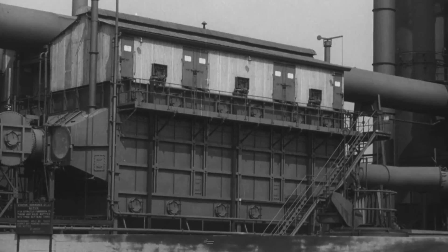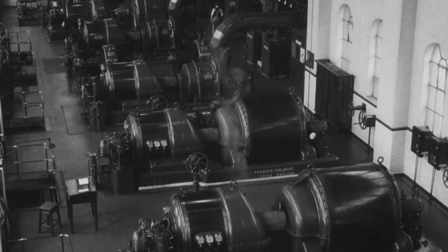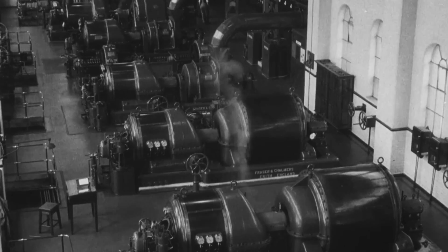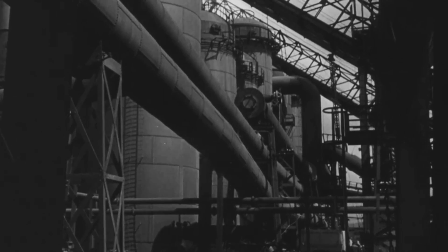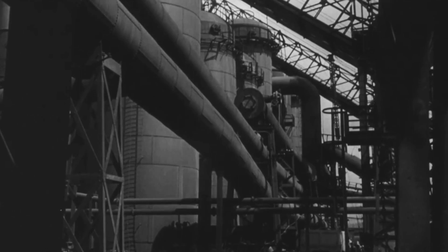Blast furnace gas is used for under-firing the coke ovens, but it is also an important factor for raising steam, which drives the turbo-electric generators and the turbo blowers which produce the air blast. And for heating the Cowper stoves, where the temperature of the air blast, before it enters the furnace, is raised to 1,300 degrees Fahrenheit.